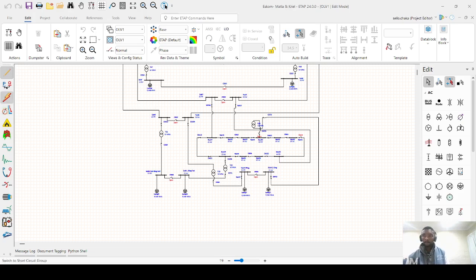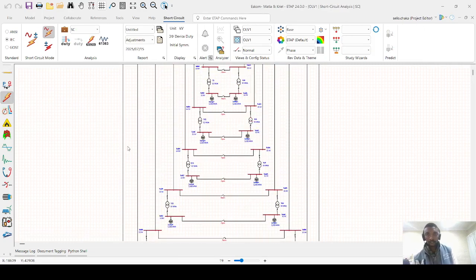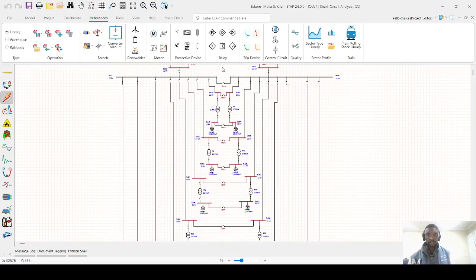So now in this section I provide a detailed analysis of the short circuit fault level results for the interconnected distribution network, modeled for the Matla and Kriel power stations using ETAP. The review covers all primary and secondary busbars across the 22 kV and 11 kV substations in both normal and N-1 scenarios.